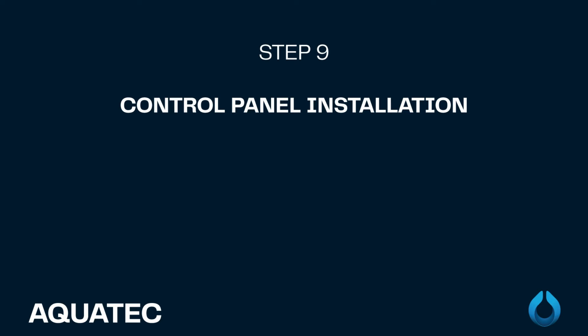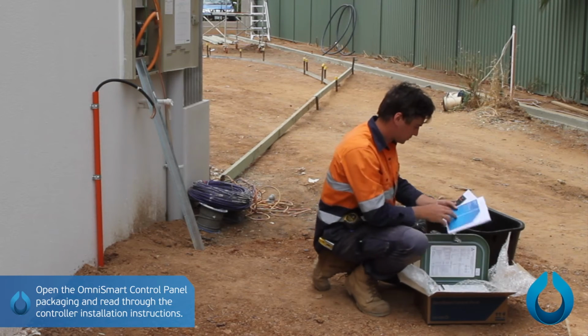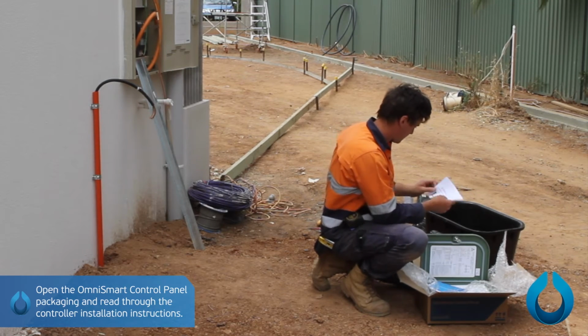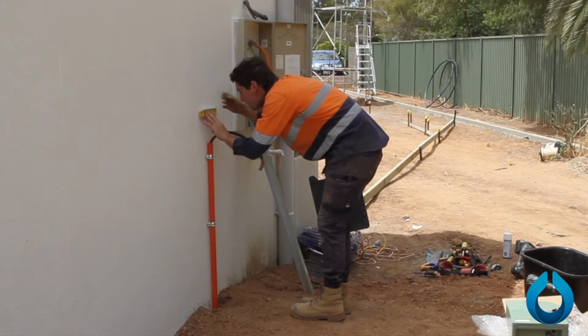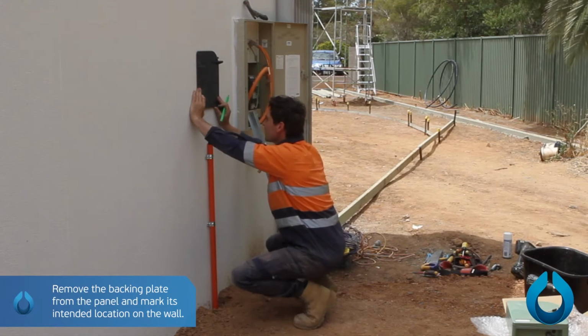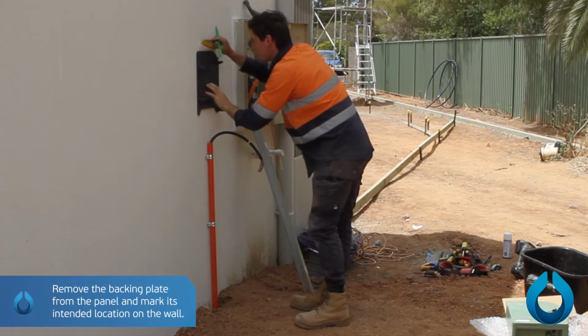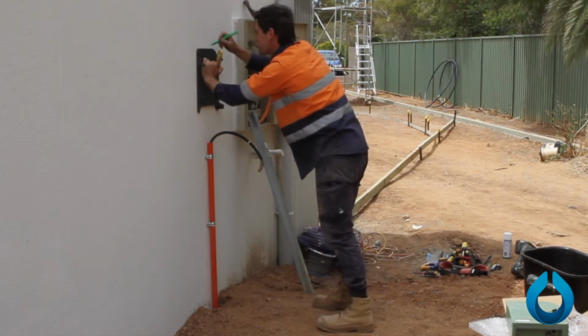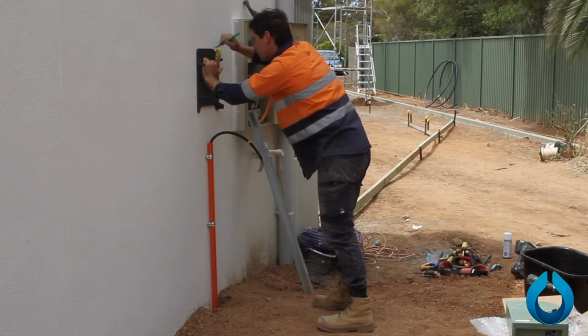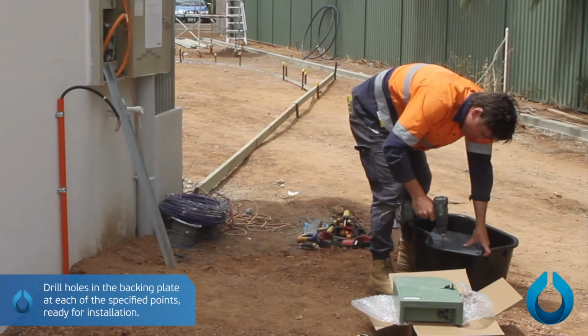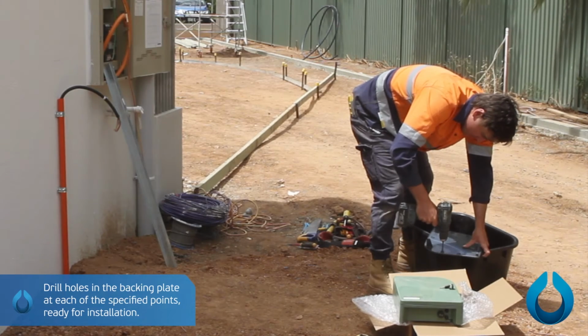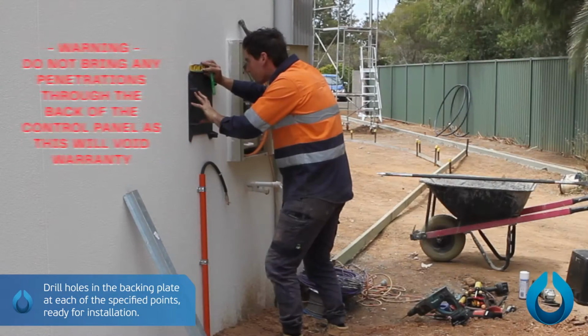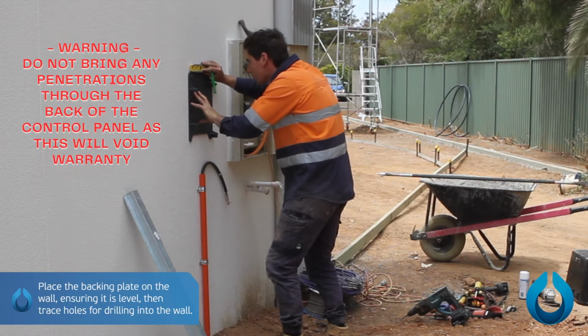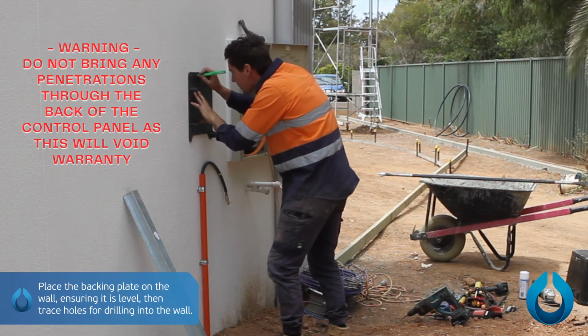Step 9. Installing the control panel. Open the Omni Smart Control Panel packaging and read the controller installation instructions. Mark out the location to mount the panel. Remove the backing plate from the panel and mark its intended location on the wall. Drill holes in the backing plate at each of the specified points ready for installation. Do not bring any penetrations through the back of the control panel as this will void warranty.